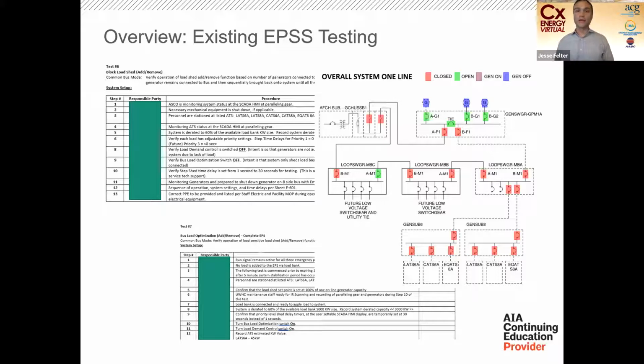When we walk away, we want that facility operator to know they've seen this system operate. The manufacturer isn't going to do it unless they're told to demonstrate the complete sequence. The installer won't do it unless it's in the spec, and I probably see a spec written like that once a year, once every other year. So the onus is on us to try to do our best to coordinate some level of demonstration. That's truly the task.